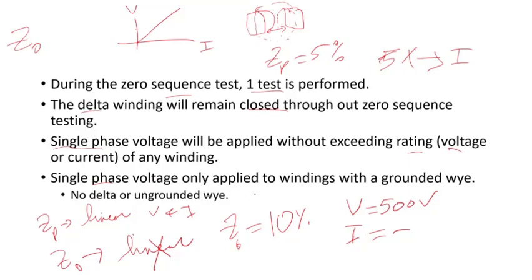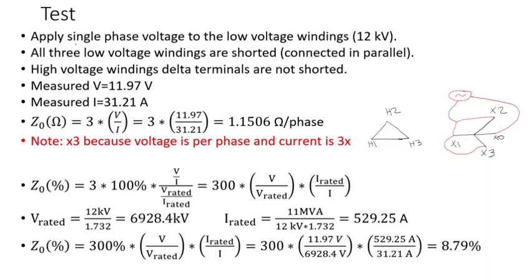Just a reminder: single phase voltage is only applied to windings with grounded Y. Since the high side is a delta, no test is applied there. Single phase voltage is applied to the low voltage (12 kV) windings; all three low voltage windings are shorted. The high voltage delta terminals are not shorted. The measured voltage is 11.97 V and the measured current is 31.21 A. Using the equation — 3 times measured voltage divided by measured current — the zero sequence impedance is 1.1506 ohms per phase.